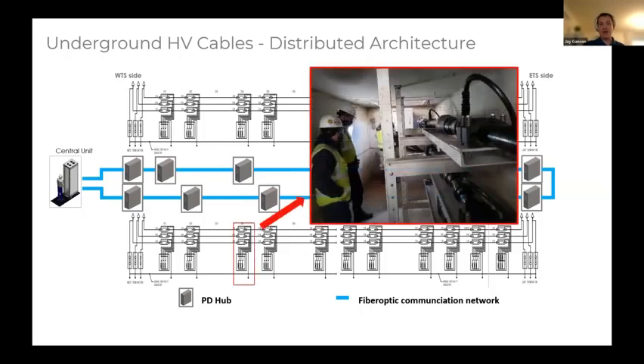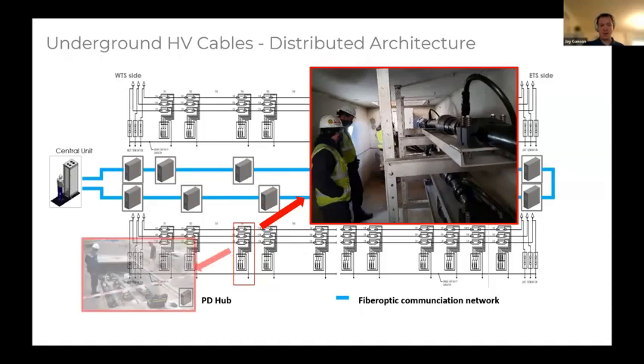Now, the splice vaults can look very different depending on where you are. Here is a picture of a 138 kV XLPE cable on a rack. That larger bulge in the middle is actually the splice itself. And oftentimes these vaults are used to protect that splice because that is the most common point of failure. You want to be able to access that. If you need to replace cables, having an easy ingress is useful. But in certain areas, in more rural environments, maybe you don't need an entire underground vault, and just a sort of shallow buried vault would be just fine. In both of these cases, we can put partial discharge monitoring equipment in here to monitor that splice.